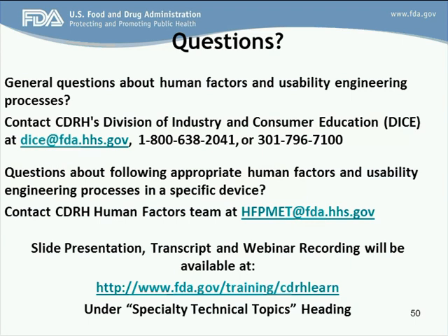Hello, this is Hannaday, and I would like to add something to what my colleague has just talked about. It's the concentration on clinical harm. Sometimes it can be a delay of therapy, or some of the harm may be a little benign, because if a device misdiagnosed a disease or condition, that is also a harm, because it's a misdiagnosis, and we have to have data for that.